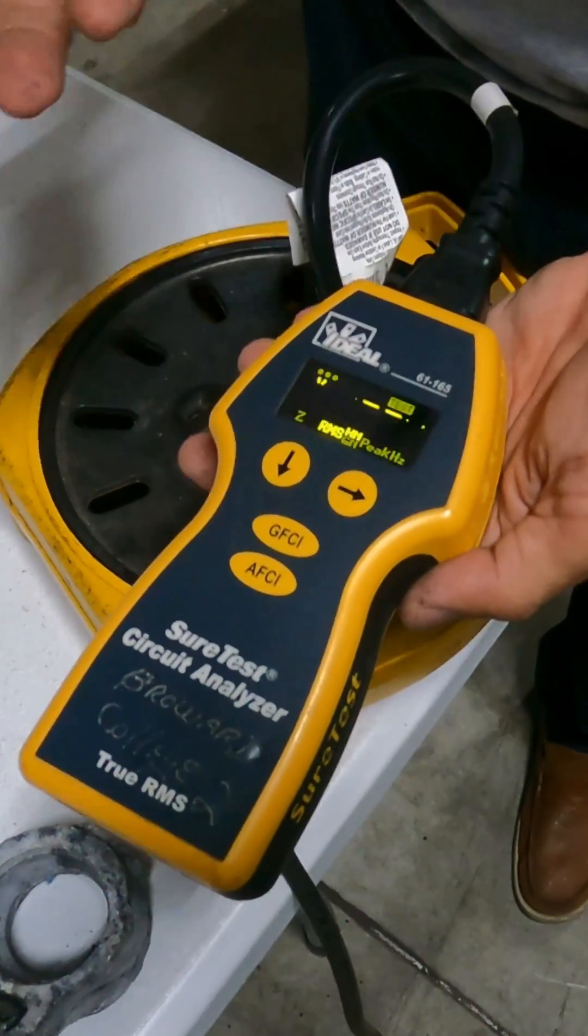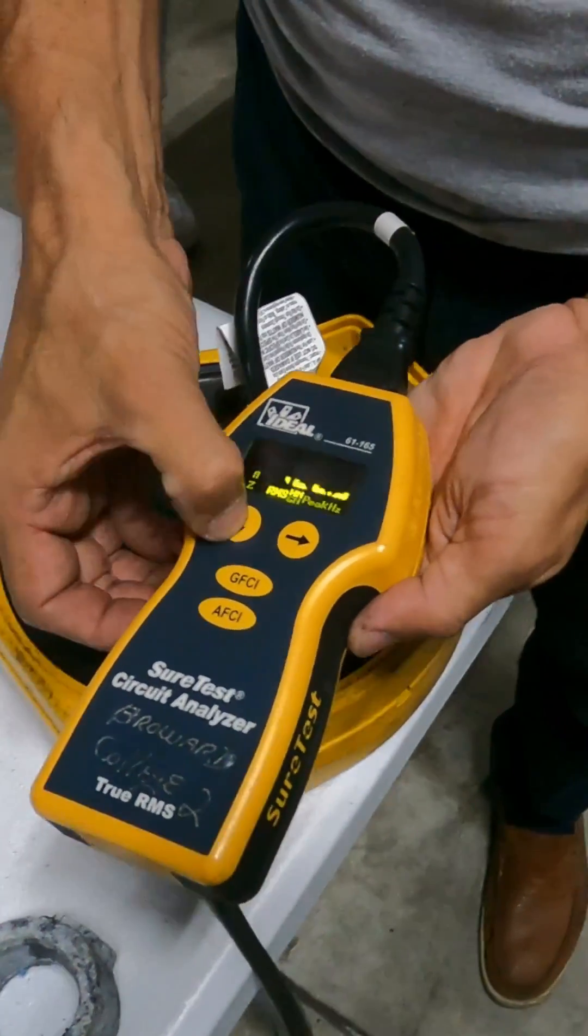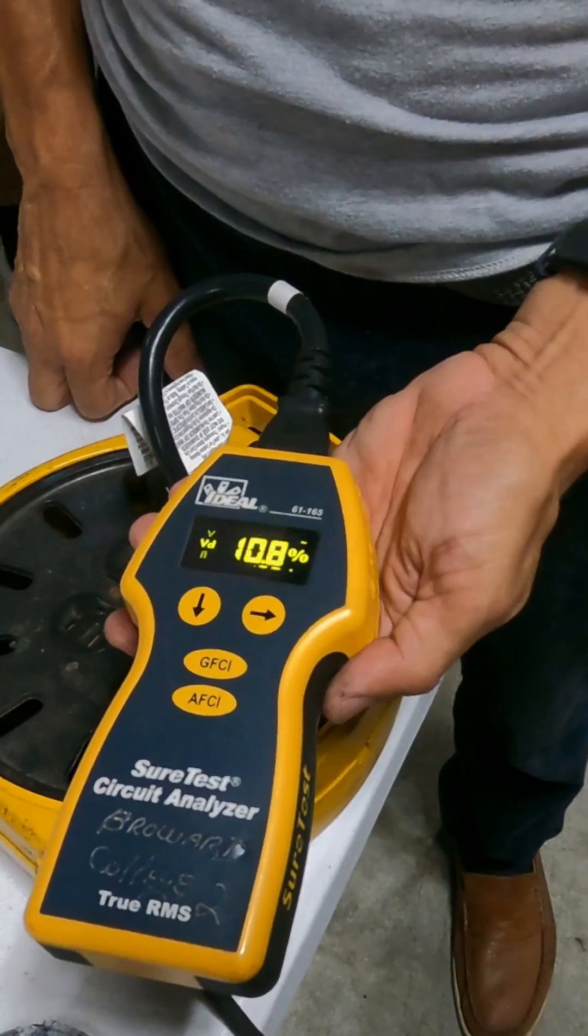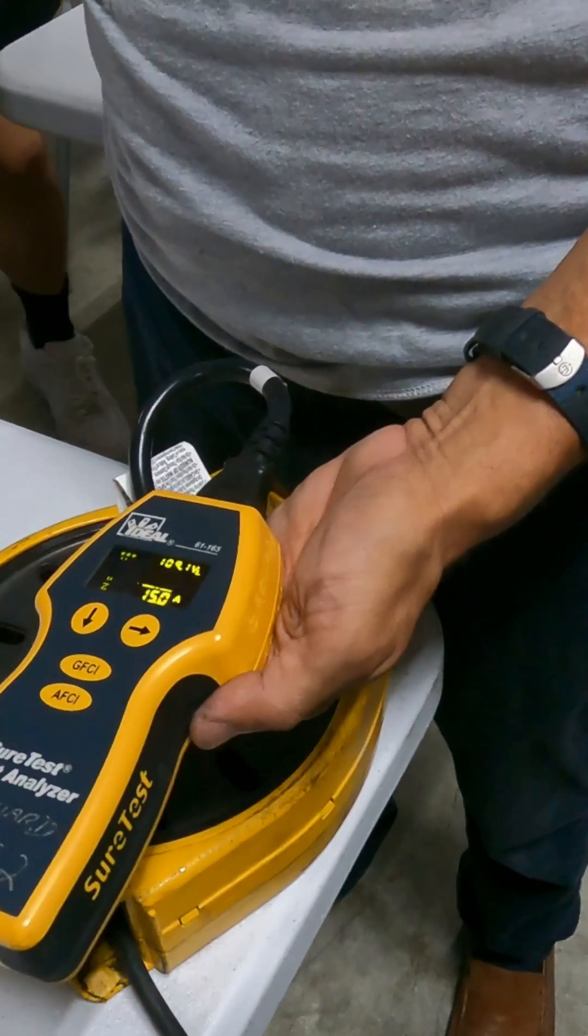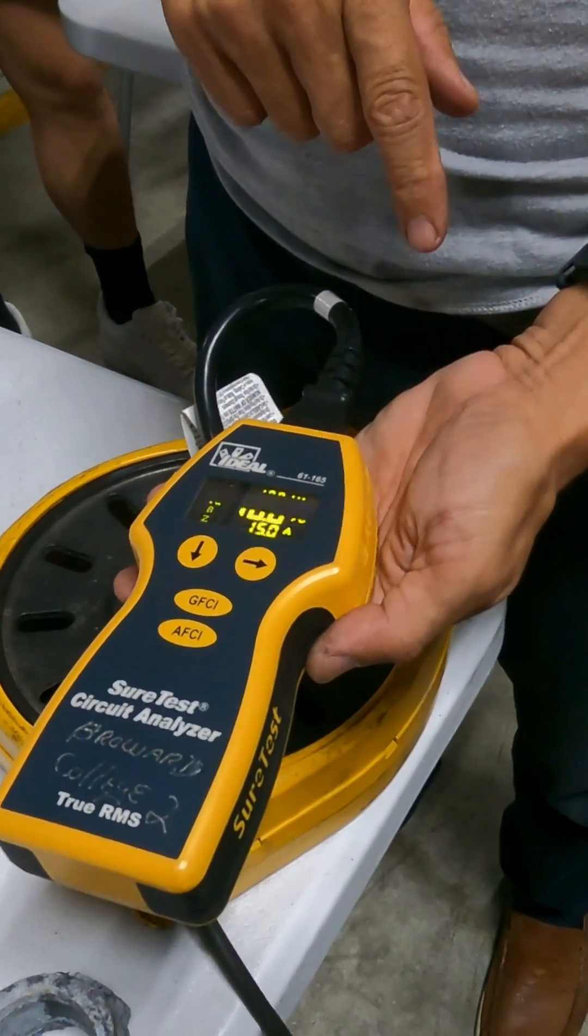We are going to check voltage - voltage is good - but voltage drop is 10.8 percent. You know, a lot of cable, a lot of wire. It went from 1.2 up to 10.8. That's a lot, no?